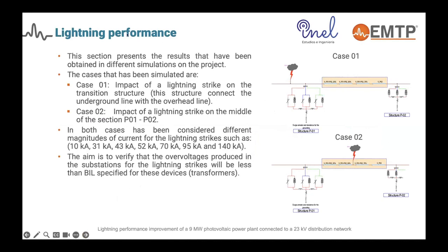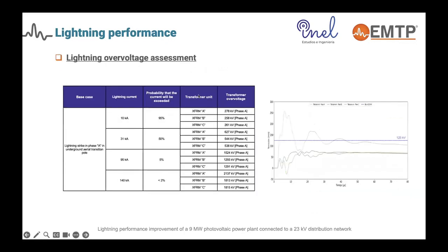There is a recommendation in IEC standard Part 4 on insulation coordination which gives guidelines for representation and calculation of transients at different frequencies, including a relationship between current magnitude and front time. For the tail time, we set it to a fixed value because this parameter does not significantly influence the maximum overvoltage, but it is conservative in terms of energy dissipation. After having an appropriate model of the real case, we performed the first scenarios — there are plenty of scenarios, but I am showing two key cases: the impact on the structure and in the middle of the first line span.